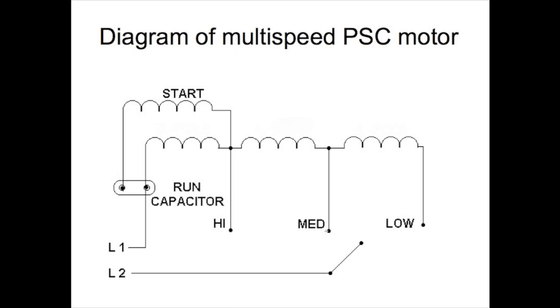Then if I go to a medium, there will be a longer winding, more resistance, lower speed. Actually, lower amp draw, which equates to a lower speed.